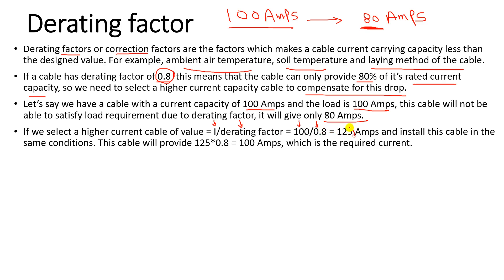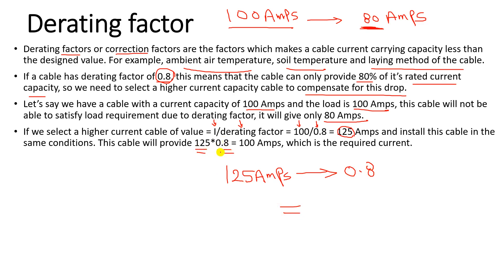With a load of 100 amperes and a derating factor of 0.8, we need a cable rated at 125 amperes (100 ÷ 0.8 = 125). A 125-ampere cable under the same derating factor of 0.8 gives 125 × 0.8 = 100 amperes — exactly the required load current. These derating factor values can be found in the tables provided in the cable catalog.